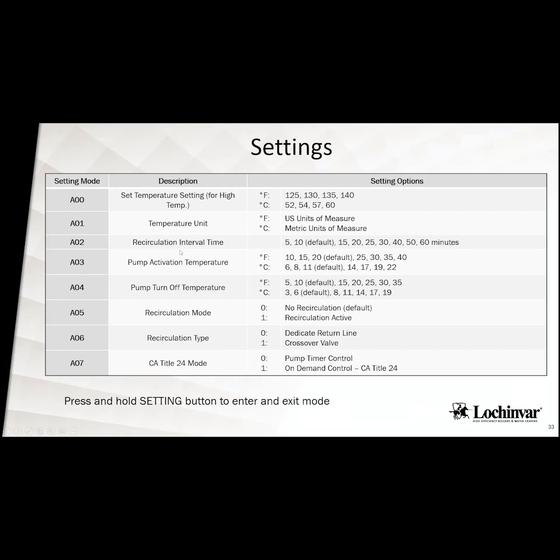The recirculation interval time is going to come set at a default of 10 minutes. So once that pump turns off, it's not going to allow that pump to turn on again for another 10 minutes, even if the temperature drops. It's going to lock it out for at least 10 minutes. The pump activation temperature is going to come set at a default of 20 degrees.